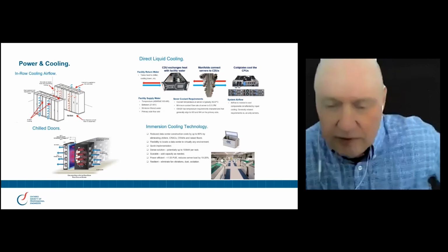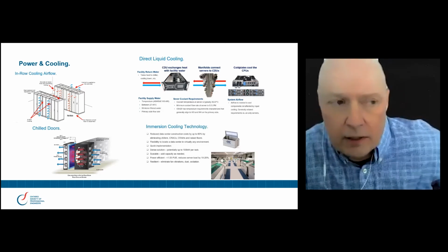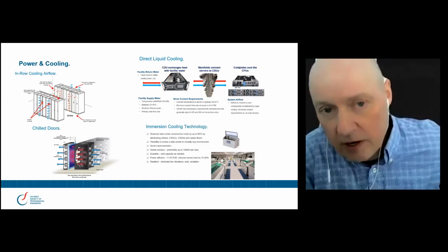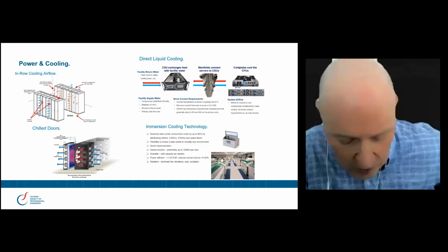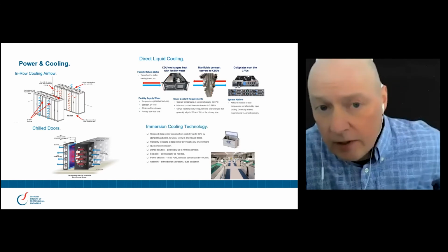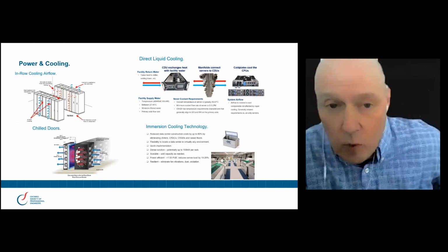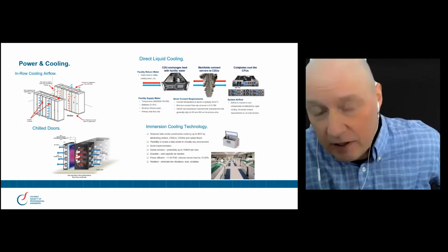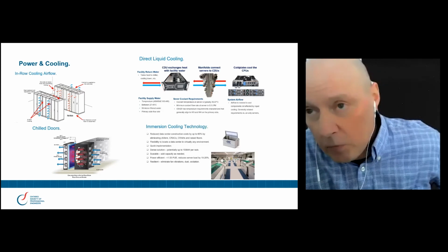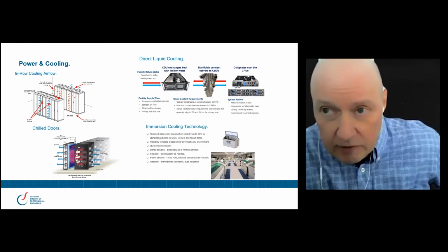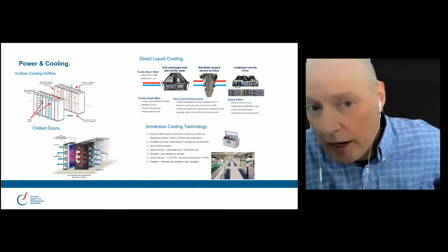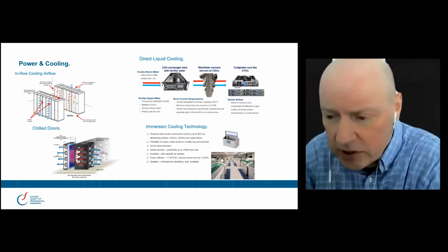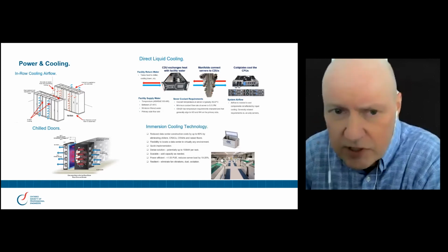To put this into perspective, I showed you some of the components that are currently available. The currently available GPU, for example, state of the art, is a 400-watt device. On the horizon, there are 1,000-watt GPUs, which is a tremendous amount of heat in a single chip. Realistically, anything above a 500-watt part is going to have to be liquid cooled. You're running up against the bounds of physics at that point.